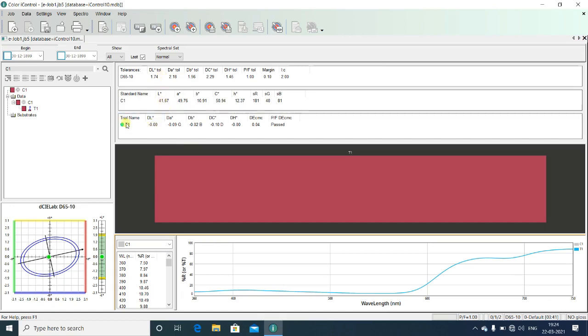On the basis of that, it will calculate the error of this sample. As it is the same sample, you can see the delta value is nearly equal to 0 for every value. We can also see a pass or fail here, meaning whether the test sample is under that tolerance limit or not. If it is under the tolerance limit, it will pass the test. Here it will show passed. If it is beyond the tolerance limit, it will show failed. So now let's take another test sample and test.